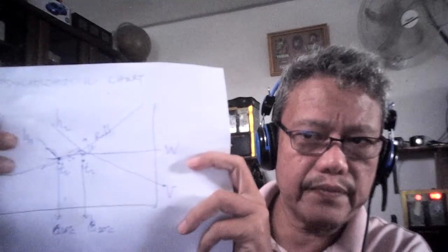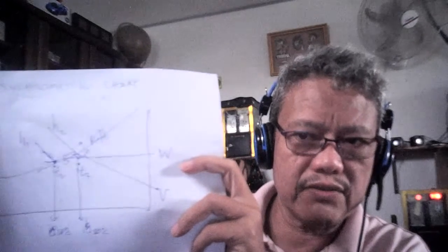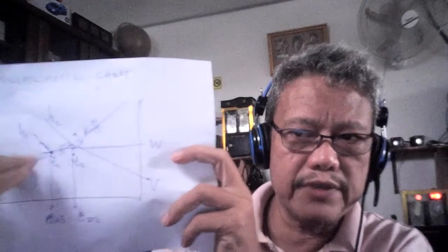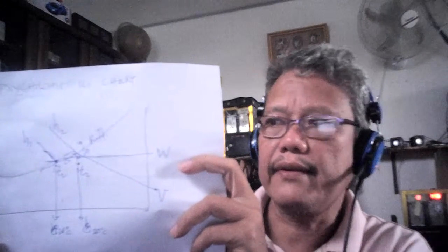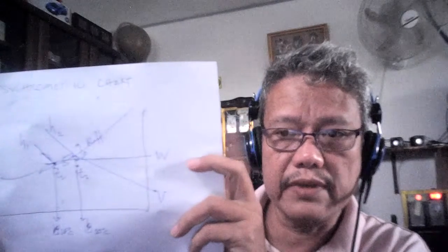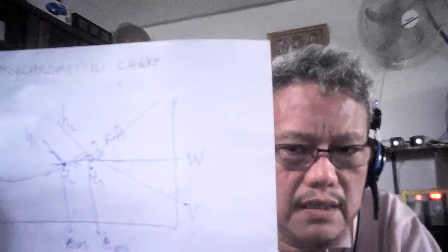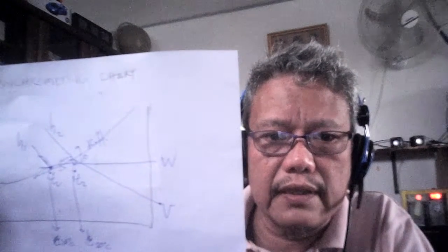From that point, you can get the enthalpy, the H1 and the H2. And by projecting it to the right side of the chart, you will see the humidity ratio, which we call the W, in terms of kilogram water vapor per kilogram dry air. And as you drop it downward, you can also see the specific volume in cubic meter per kilogram.